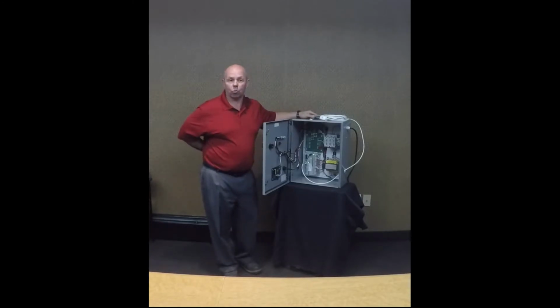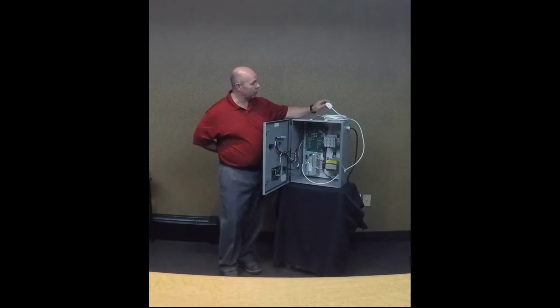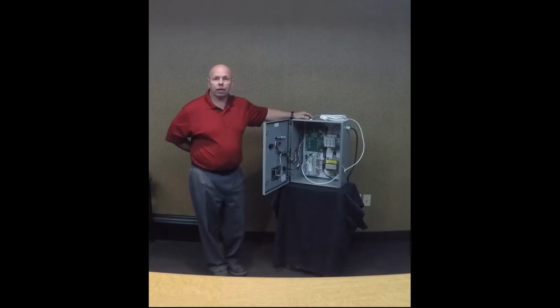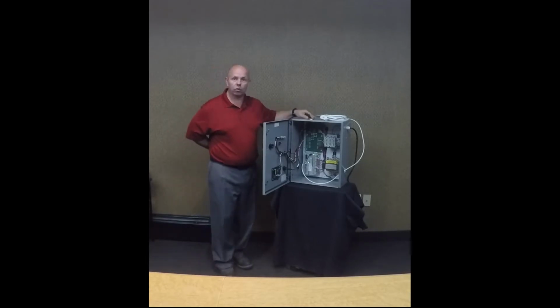circumference along that rope. As you'll note, the end of each sensor, we have a little indication light here. This is the built-in test feature of the P1 arc flash relay that shows that the system is actually functioning. The relay itself sends out this signal, the detector will sense that, and then come back in and measure that. If the relay does not see this indication, then it means that it's malfunctioning and will go offline. The P1 arc flash relay system will detect an arc flash event within 1 millisecond. That can be detected again with the point of use or the rope sensors.